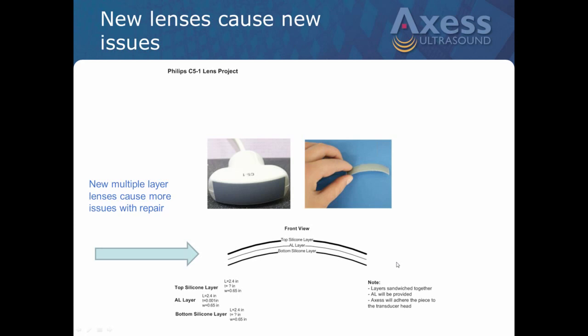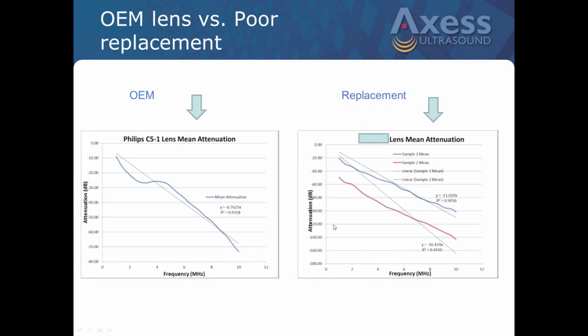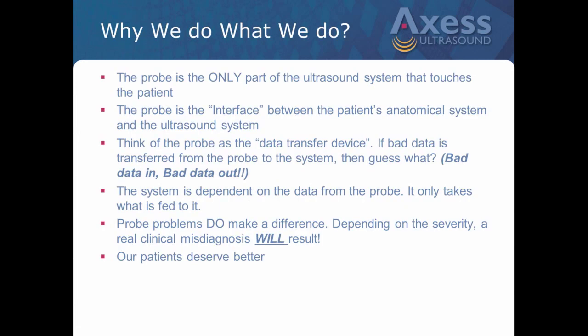We have a full TEE repair lab, and we replace arrays and cables and rework everything. But the one thing about TEEs, and I'm showing you some of the problems here. Again, bite marks here, corrosion and things up here, scratch marks on the tip. A transesophageal probe will work forever if it's taken properly care of. It won't fail any more than any other probe, but we rarely ever see TEE probes that are well taken care of. So by all means, if you're having any problems, especially with punctures in the insertion tubes, scratches on the lens and tips, make sure they're using bite guards. And if they're not, then they need to give you a good reason why not.